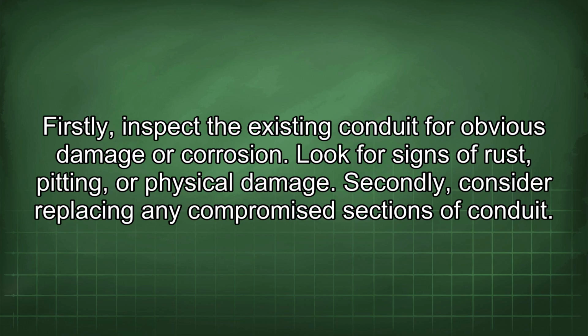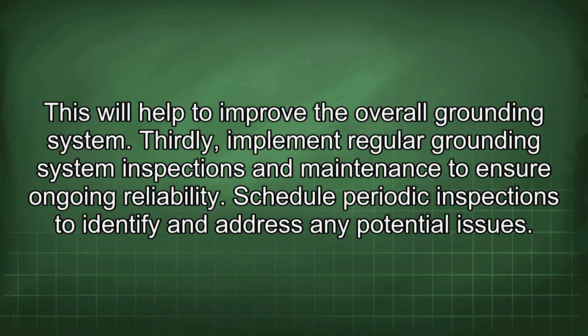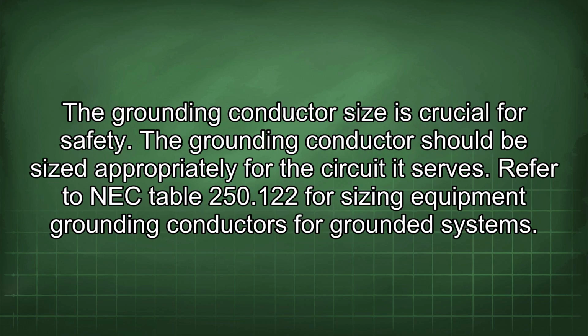Secondly, consider replacing any compromised sections of conduit. This will help to improve the overall grounding system. Thirdly, implement regular grounding system inspections and maintenance to ensure ongoing reliability. Schedule periodic inspections to identify and address any potential issues. The grounding conductor size is crucial for safety. The grounding conductor should be sized appropriately for the circuit it serves.